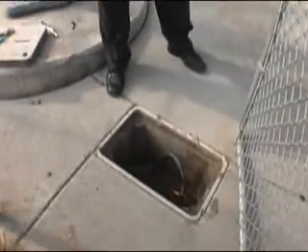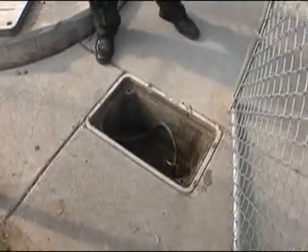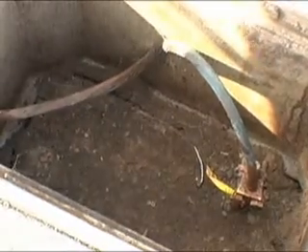This is where the actual deep ground was driven and then connected into the ring around the tower base. This deep ground is between 100 and 110 feet into the ground. And as they were driving it, we actually have a chart of the resistance. As the resistance was going down, we were shooting for 3 ohms or less.